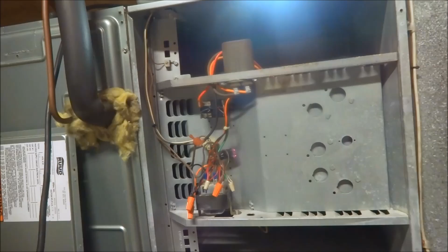Okay. And then we got the common for the contactor. We got the common for the relay. We'll pull that relay in. Okay. We got the common coming off the transformer. And then we got the common for the contactor outside. Very simple. All I gotta do is tie all these wires together, put a pull tie on them, and I can button it up. We'll be good to go.